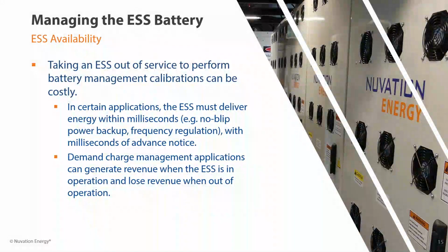An energy storage system must deliver energy in some applications within milliseconds. For example, if you're doing a resiliency application, providing power to a telecom center or a hospital, they need to design an ESS with a PCS that offers full transfer without any glitches in power. You don't really get advance notice on that, so you have to be able to do it near instantaneously.